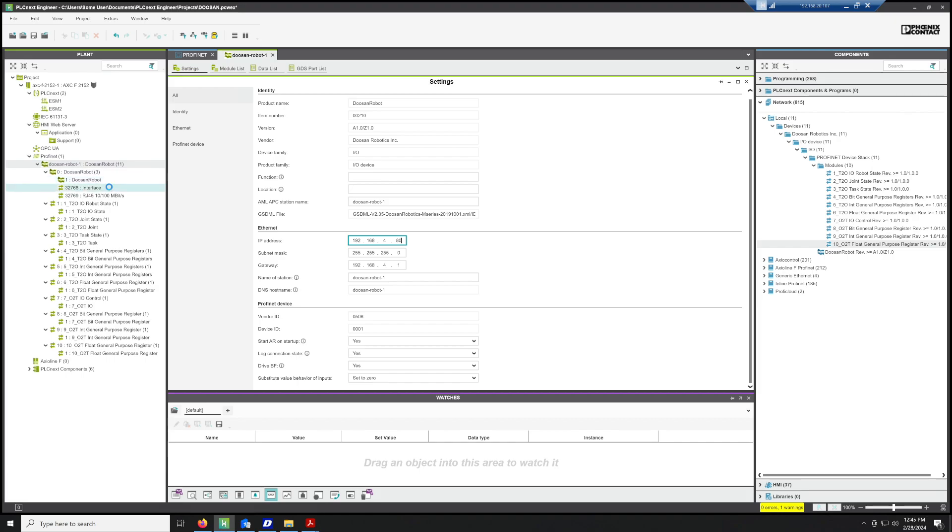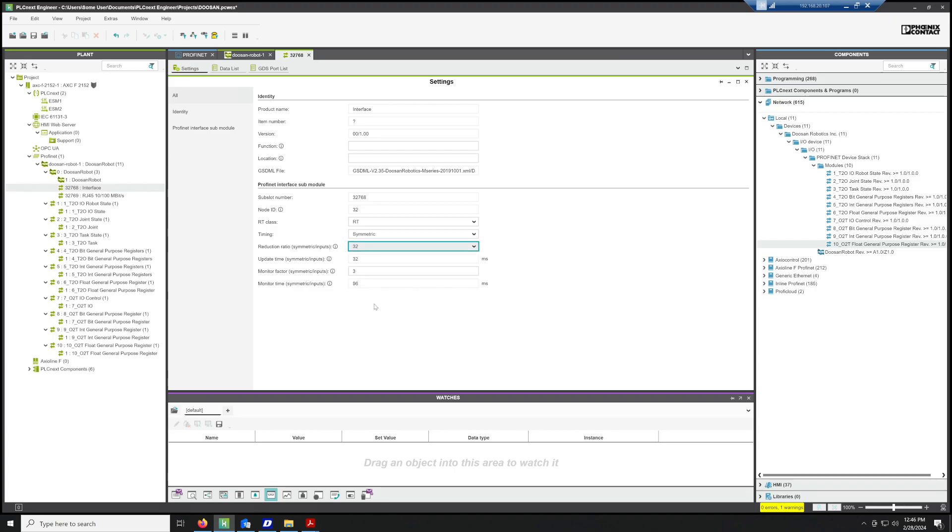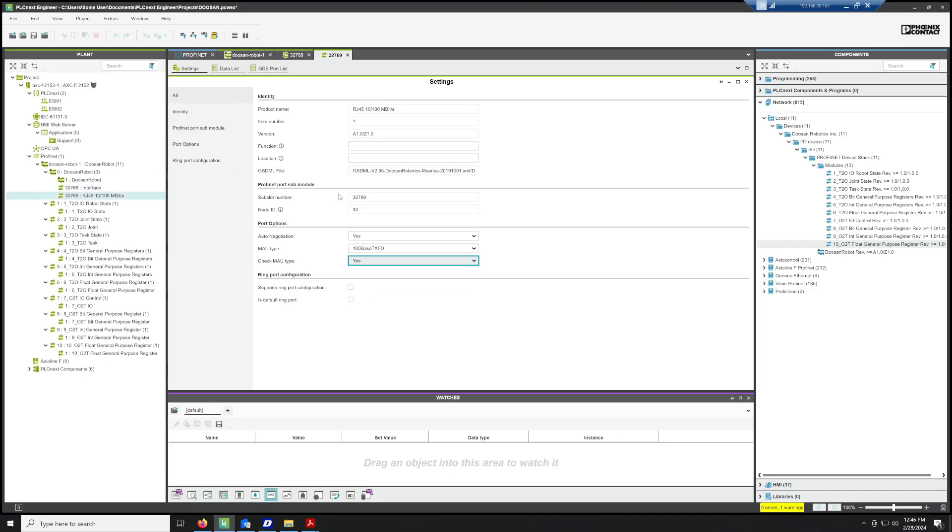In the interface settings, we'll have to change the update time from 8 milliseconds to 32 milliseconds, and then we'll just have to change one other setting. This MAU type, we have to change to No.